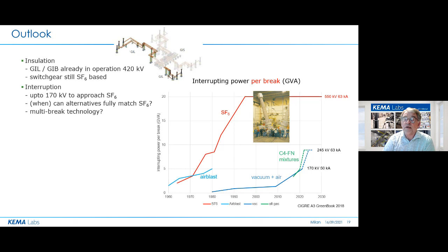Looking at the interruption, it is clear that interruption without SF6 is more difficult than insulation. Several pilots are ongoing with F-gas based GIS, though in quite a few cases the rated voltage of the pilot GIS is chosen to be higher than the actual system, such as a 145 kV breaker in a 110 kV grid, to build in a margin in a first step. What remains unanswered is when and whether the alternative can match SF6 in power of interruption.